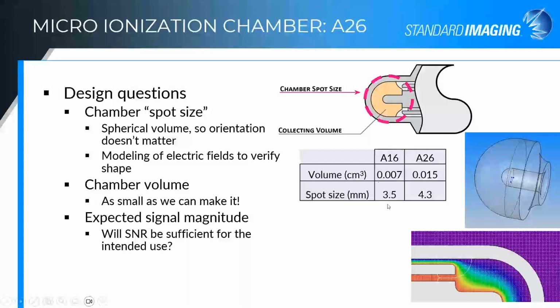In terms of volume, our A16 is our smallest microionization chamber, and it has a wire as the central electrode. So the machining values for that are a little bit different, but we're able to make that volume a little bit smaller. But if you look, the spot size of the A16 compared to the A26, although the volume is doubled for the A26, the spot size is only 0.8 of a millimeter larger. So really it goes down to the same sort of small fields that even our smallest microchamber can measure, without having the polarity problems of those other microchambers, including the A16.